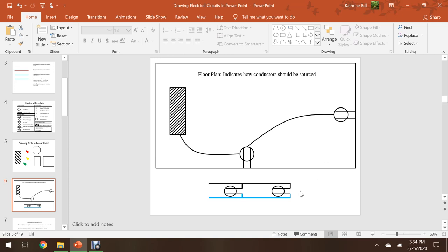Down below, we have a ladder diagram, or ladder logic. Looking at the ladder logic, we've got a black line. This black line represents the ungrounded conductor. This is one 120 volt phase coming from a circuit breaker inside the service entrance panel. You'll notice that it runs uninterrupted. You'll notice that we tap into that conductor and carry power to each duplex receptacle individually so that current does not have to pass through one duplex receptacle in order to get to the other. This is a parallel circuit. Our grounded conductor or neutral conductor, which is our white insulated conductor, likewise returns back to the service entrance.